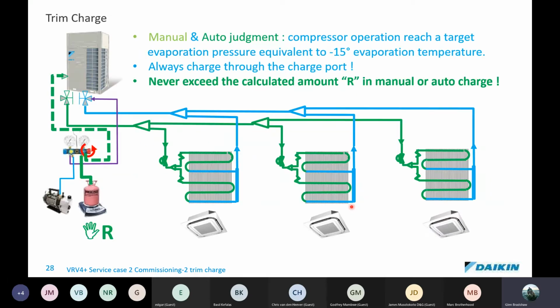So moving on to that, manual and auto charge judgment. The compressor operation will reach a target evaporating pressure equivalent of -15 degrees, and always charge through the charge port. Now remember, we showed you in the images that there's a charge port, not through the service valves, but to the right of them, and through that charge port is the only way that you can charge.